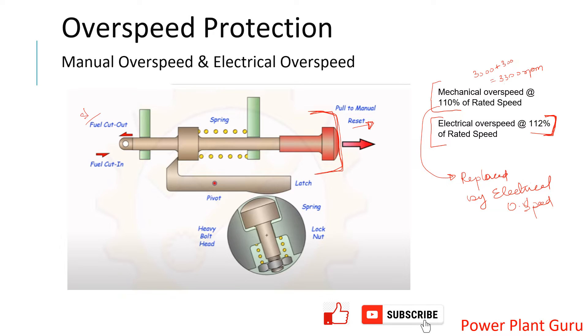The mechanical overspeed trips by cutting fuel in a gas turbine or steam in a steam turbine. Basically, it opens a trip oil drain so that the trip oil circuit is emptied out, causing the main stop valve or ESV to close. The ESVs are held open against that oil pressure, so if the oil is drained, the trip valves close — or in a gas turbine, the fuel stop valve closes.